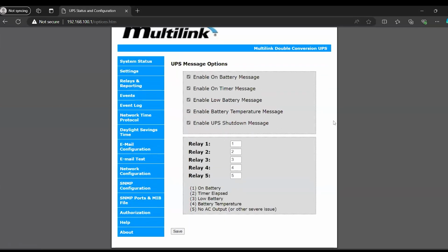Relays and reporting. We do have the 5 dry contact relays on the front of the UPS, and these are configurable. All you need to do is click on which relay you want and set it 1 through 5. It's pretty straightforward. Straight out of the factory, Relay 1 is set to condition 1, which is on battery or inverter mode. Relay 2 is condition 2, and so on. So we have on battery, time elapsed, low battery, battery temperature, which is if your battery temperature is out of range, and then also if you have no AC output or another severe issue. And Subi will show you the dry contact relays when we get to the live demonstration.